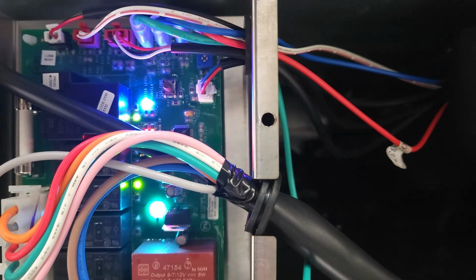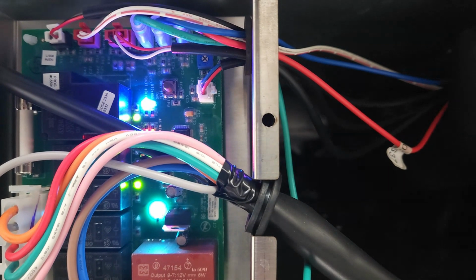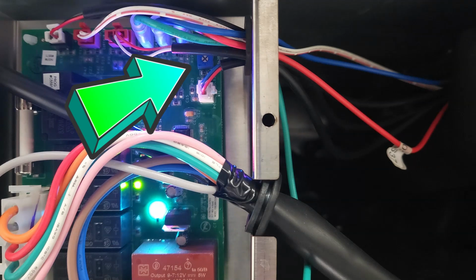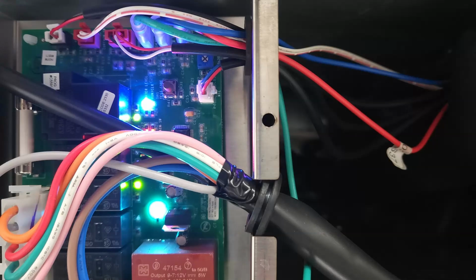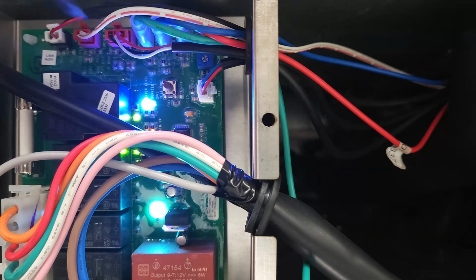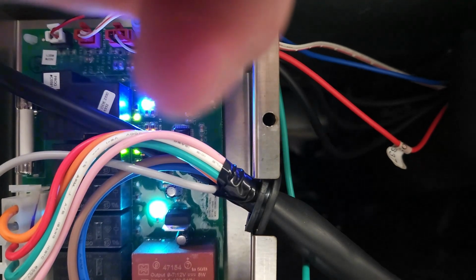We now have access to the control board. At the top of the control board there is a small blue box called a potentiometer. In the center of the blue box you will find a screw. Use a small screwdriver to adjust the screw in the blue box. 1/8 of a turn clockwise will add around 10 seconds to the drain time. And counterclockwise will remove 10 seconds.